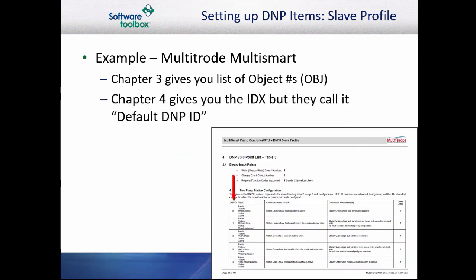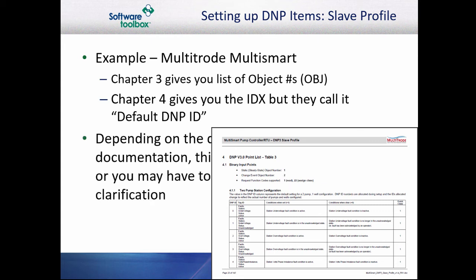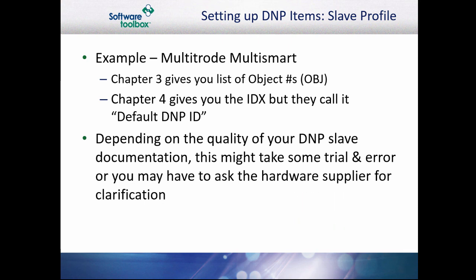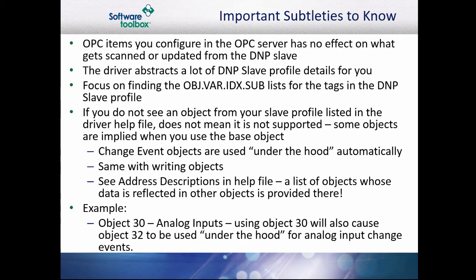Chapter 4 gives you the index — though they call it the DNP ID — conditions when set and clear, and the event class for the point. In a proper DNP3 implementation, your number of tags in the client or server will have no effect on what points are scanned or updated from the DNP3 slave. The driver abstracts a lot of the DNP3 protocol and slave profile details, so you don't have to get caught up in those.